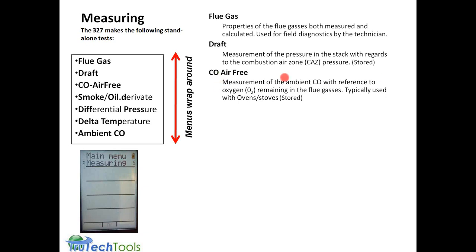The CO air-free measurement is a measurement of the ambient CO with reference to the oxygen that's still available in the flue gases. This is typically used with ovens or stoves, like an unvented appliance. And again, this is a stored parameter, which means it gets put away until you do the printout or you run the next test.